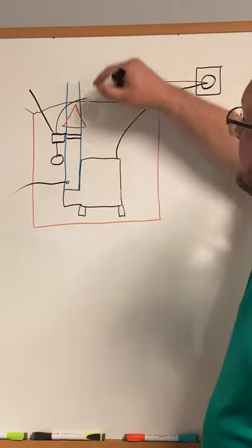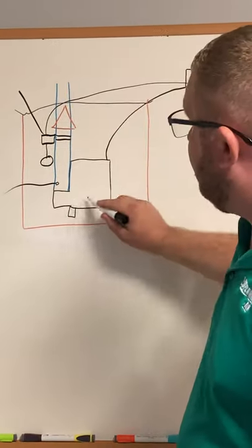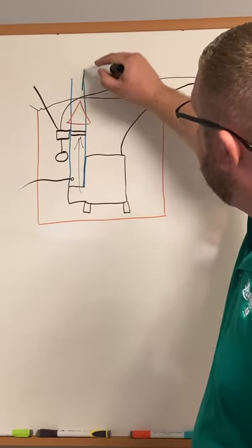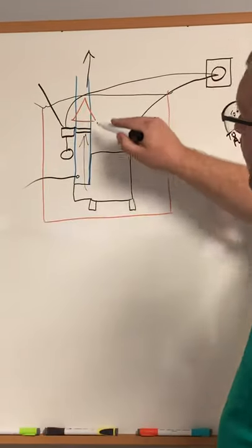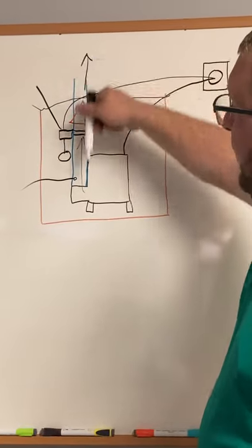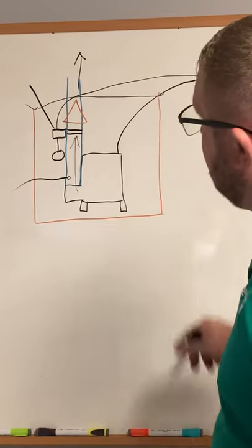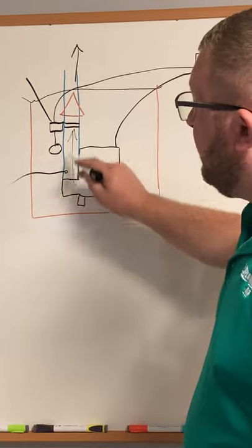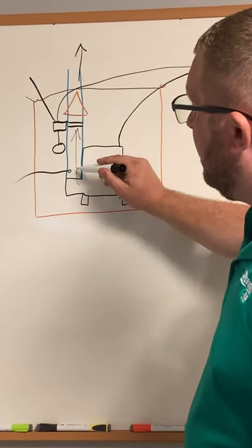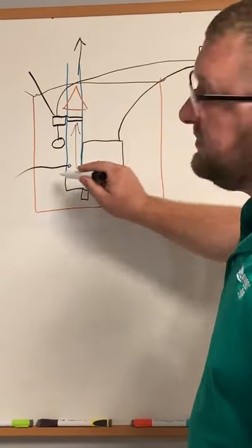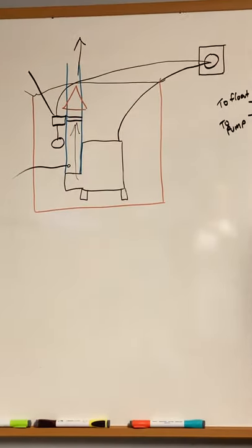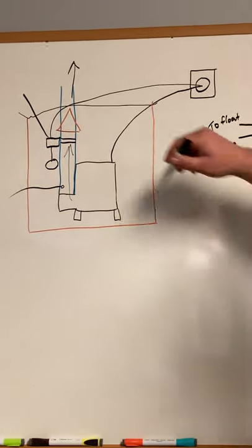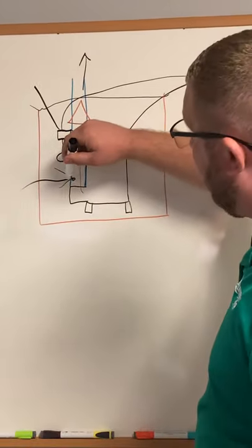So what happens is after your pump finishes pumping, the water goes out. This check valve doesn't let that water flow back into the pit. So the check valve's here stopping the water from flowing back, and this weep hole is supposed to allow this water that's in the pipe and built up in the pump to drain out so the pump doesn't have as much head pressure to pump against, or what we call airlock. So with that spraying out, that's completely normal.